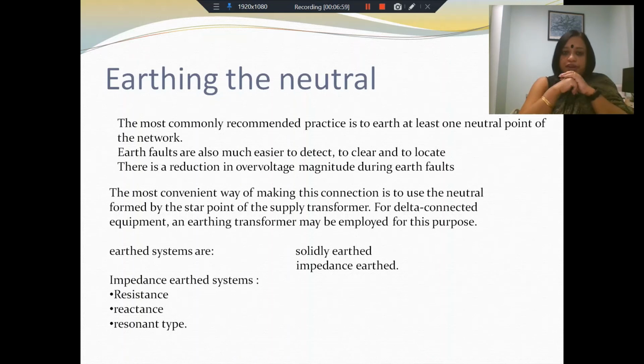It is also very convenient to make the connection, especially if you have a star connection. Then you just take the neutral out, use the neutral from the star point of the supply transformer and connect it to earth. If you do not have star connected equipment but you have delta connected equipment, you will need a separate earthing transformer which is star connected, and the neutral of that earthing transformer will be used to earth the system.